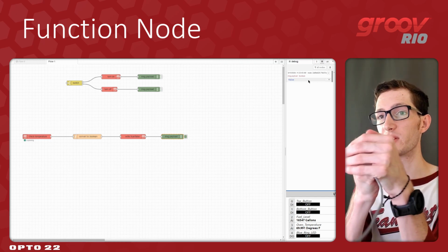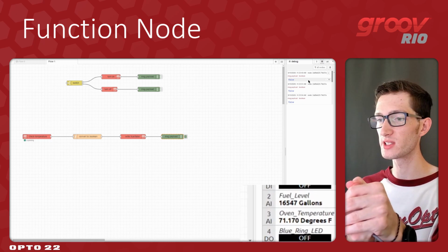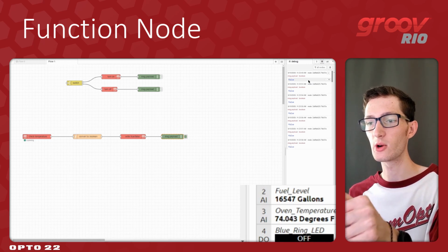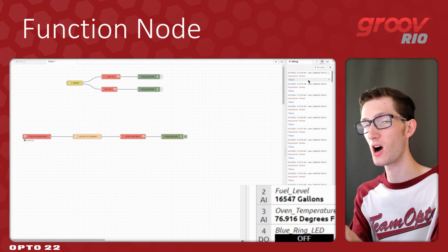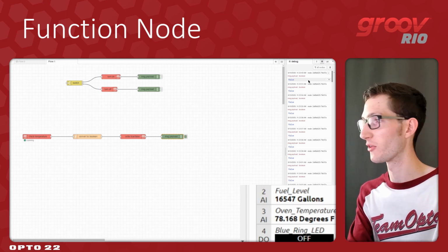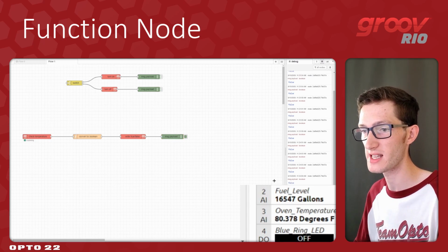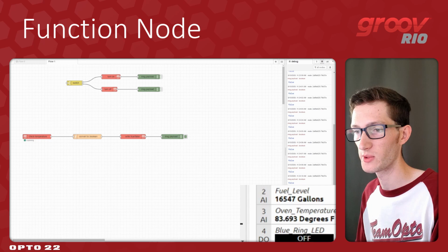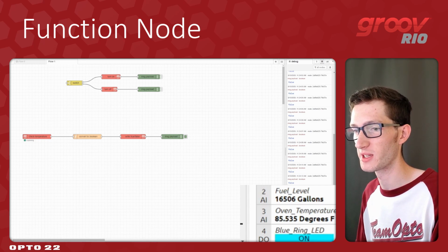Again, if I were to grab the temperature sensor, we'll see it start heating up. And we're continually writing false because you'll see down there in the bottom right, we're still down at 70 degrees. We're increasing quite quickly, and every half degree of change, again, we're confirming off, off, off, off, and we're continually writing false. And so we'll see that continually until we pass the 85 degree mark. Should just take a second longer, and then we'll start seeing true show up, and we'll see this output get toggled. We let it cool down a little too much, it's taking a moment here, but there you go.